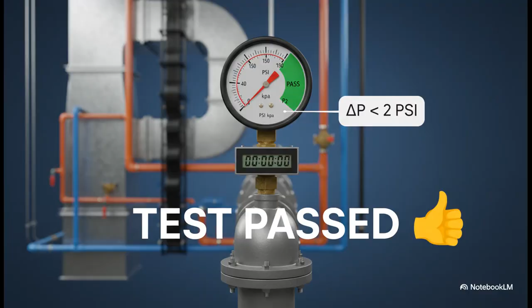A pressure test is where you fill the pipes up to a certain pressure. We'll call that P1. Wait a couple of hours and then measure the pressure again, that's P2. The difference between them, or delta P, tells you if you have a leak. And the rule is clear: if the pressure drops by less than 2 psi over 2 hours, congratulations, you've passed.